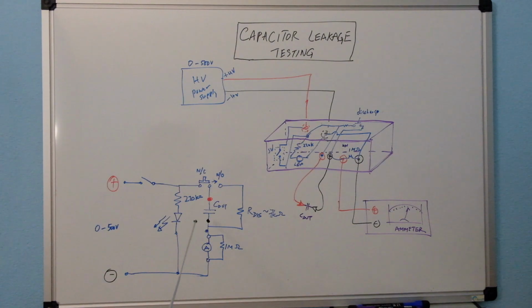One more thing I wanted to mention: if you have a very low leakage current, you can place a voltmeter over here. Once you charge the cap, using a short across this terminal here, you allow the capacitor to build up full charge, and then you remove that short and put a voltmeter here. You're going to measure the leakage through this capacitor on the return path.